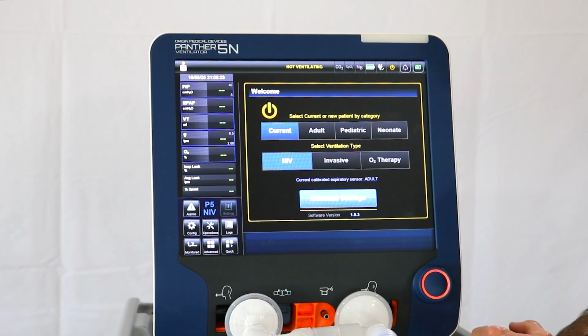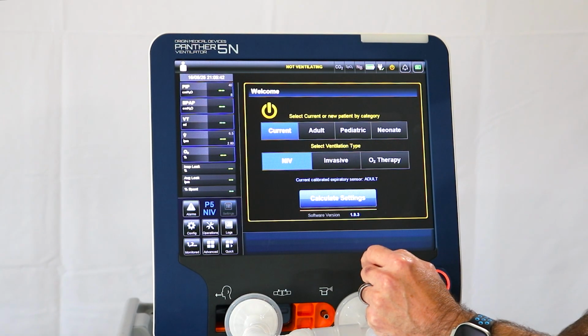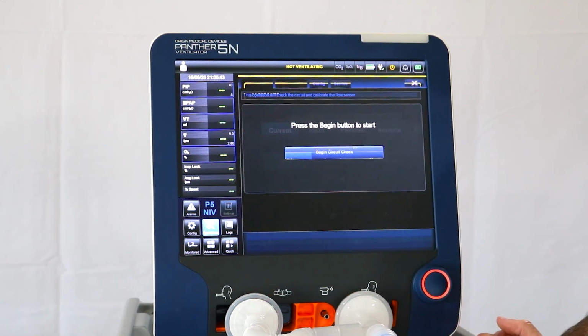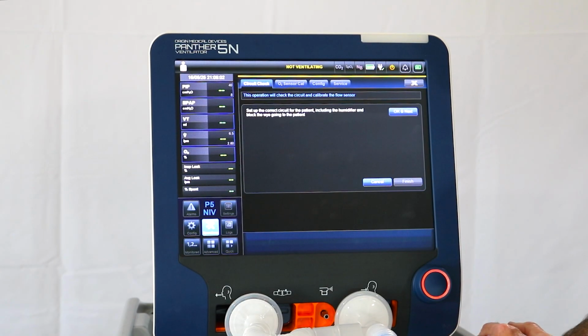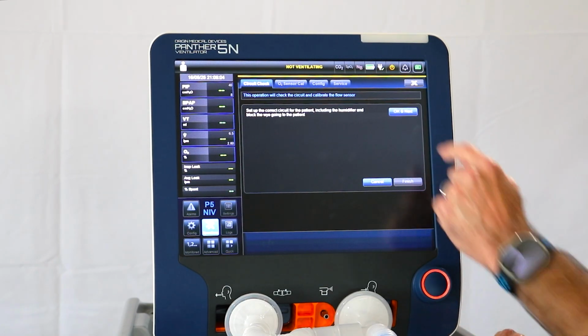Prior to the use of a new circuit and/or flow sensor on the Panther 5N, you must perform a circuit check. Press Operations in the center of the control panel. Select Begin Circuit Check. Occlude the circuit and follow the instructions on the screen.